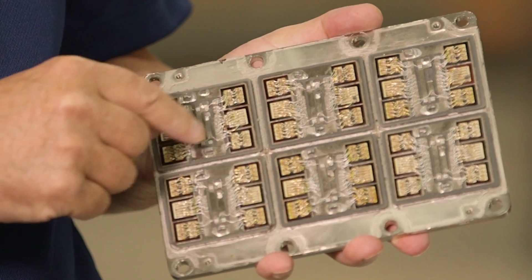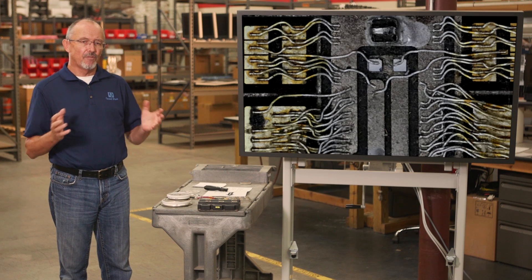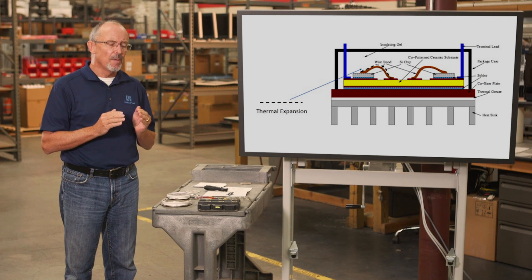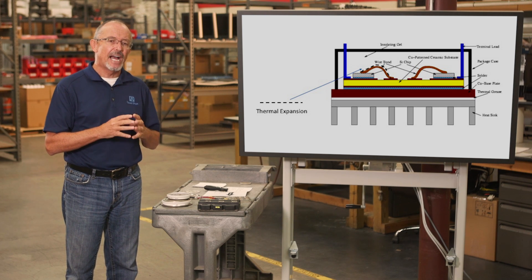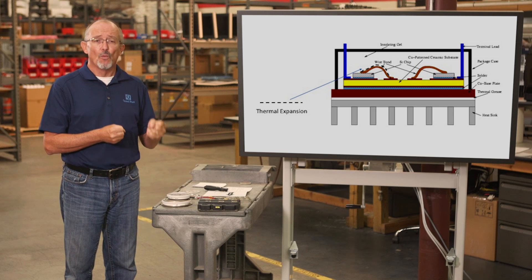However, what has been found over time is that the small bonding wires connecting to each individual IGBT tend to move during thermal transients — as you heat the device up and cool it down. So there is effectively a moving part inside the package. Over time, as that wire continually expands and contracts, it can break, and ultimately the device is no longer capable of carrying rated current or supporting rated voltage. This wire movement issue typically manifests in applications with cyclic loading — such as mill stands — with very good cooling systems like water cooling where temperatures recover quickly, and where drive sizing versus motor requirements is very tight, operating the device right around its limits.